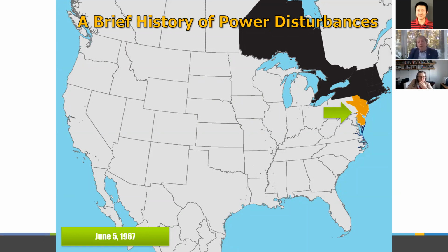Second outage was an operator error. Muddy Run pump storage plant had just been completed. We hadn't built all the transmission we needed to easily run the pumps and the generators. And when they were going from pump mode to generate mode, they were supposed to split the bus so the generators would be distributed out through the system. The operator failed to split the bus. We had an overload that occurred. Lines started tripping. We lost 2 major generating stations connected at 500 kV. And more seriously, the frequency dropped to 53 hertz before the cascade was over and stayed there for a while. So you worry about damaging generators, and this was before our load shedding under frequency relaying was put in place.